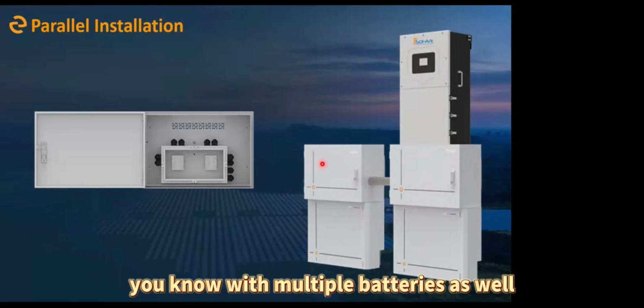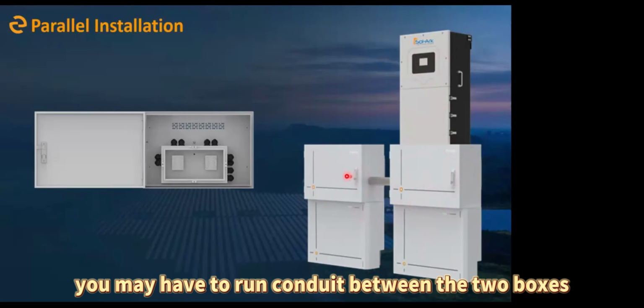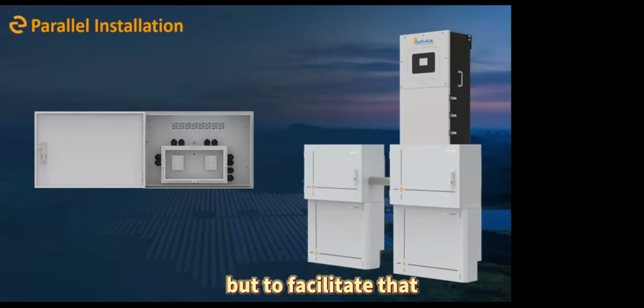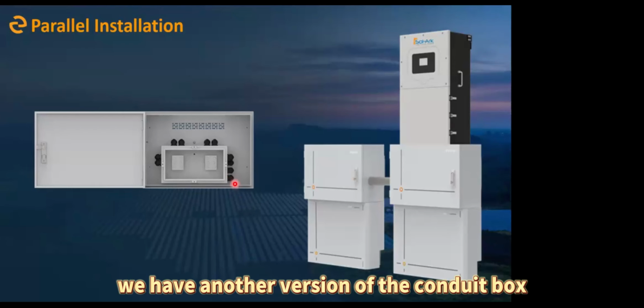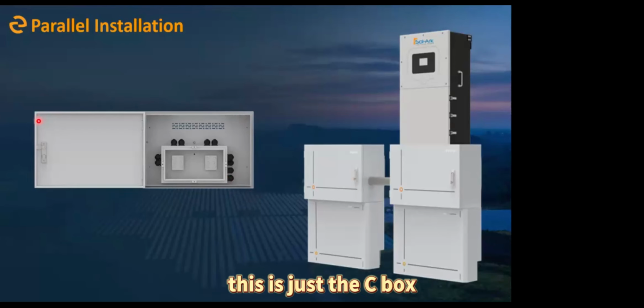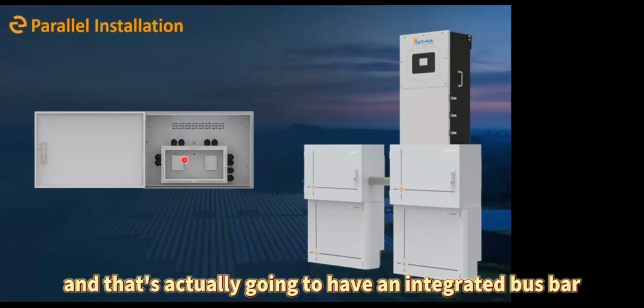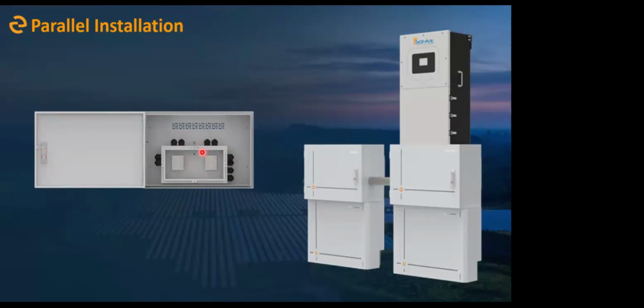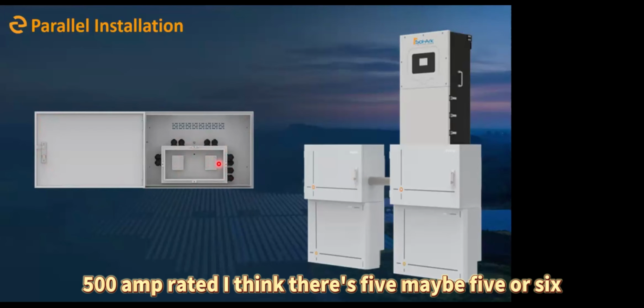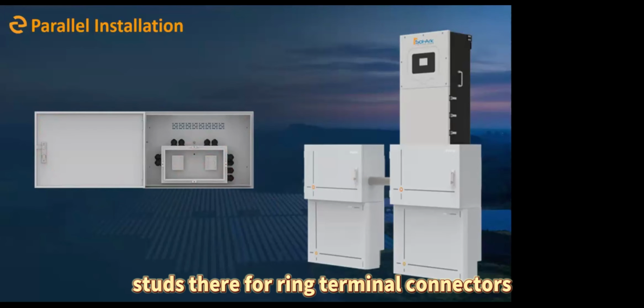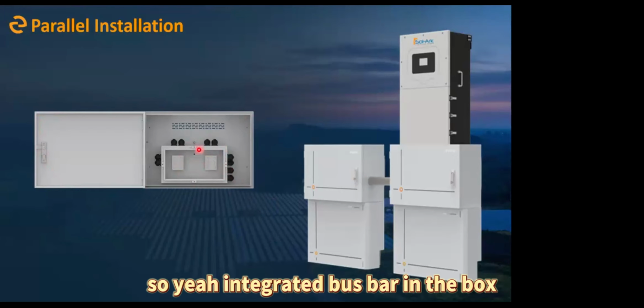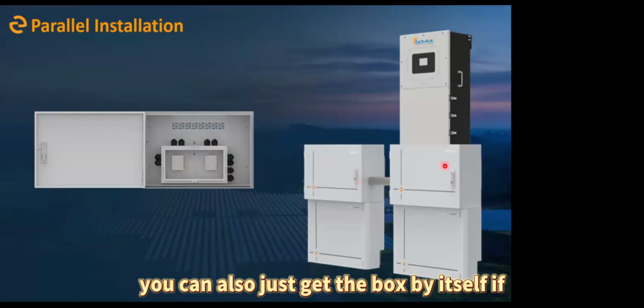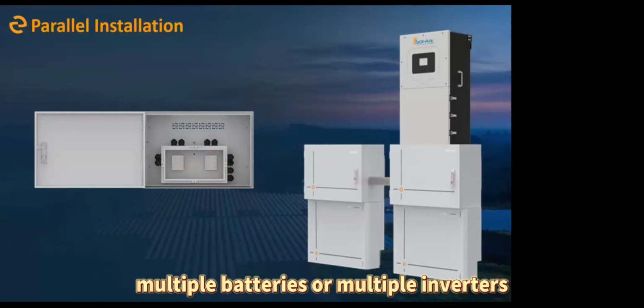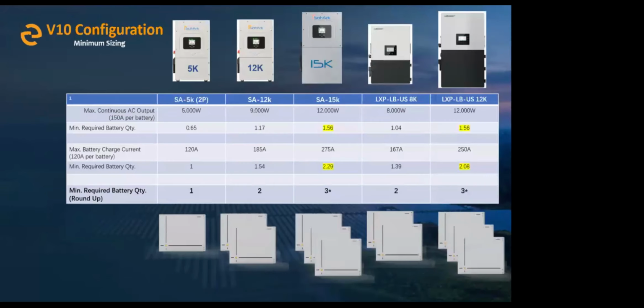And with multiple batteries as well, you may have to run conduit between the 2 boxes, but to facilitate that we have another version of the conduit box - this is just the C Box, and it's actually going to have an integrated bus bar inside, 500 amp rated. I think there's 5, maybe 5 or 6 studs there for ring terminal connectors. So yeah, integrated bus bar in the box. You can also just get the box by itself if you're not combining multiple batteries or multiple inverters.